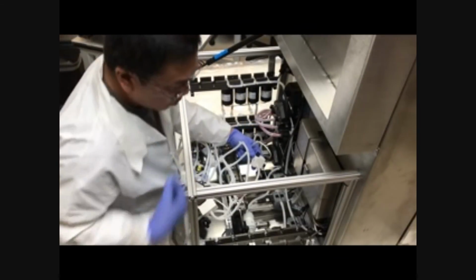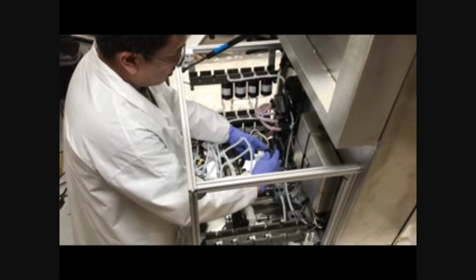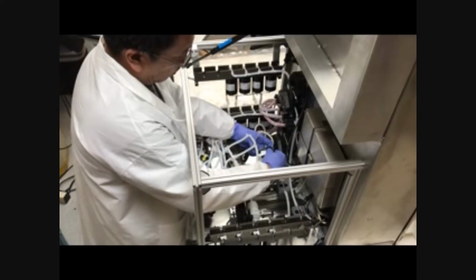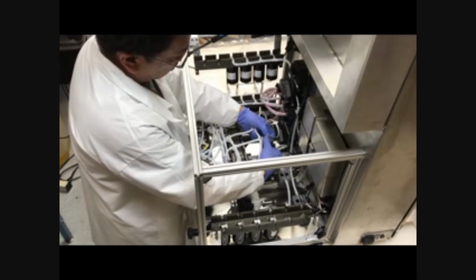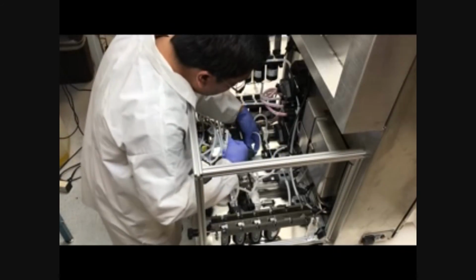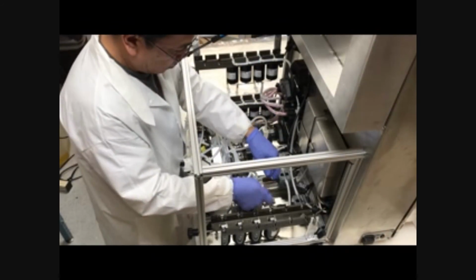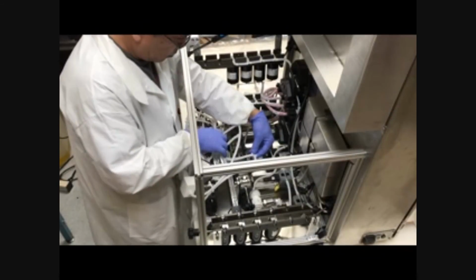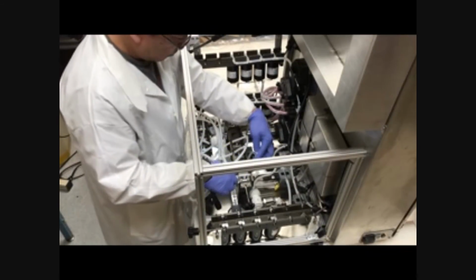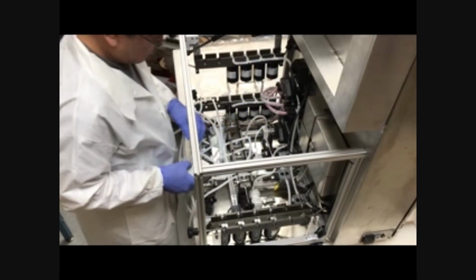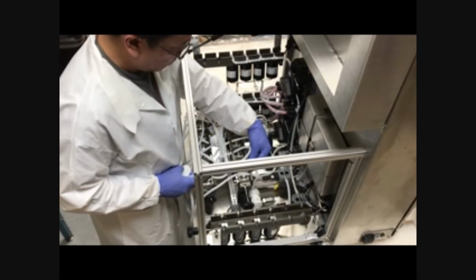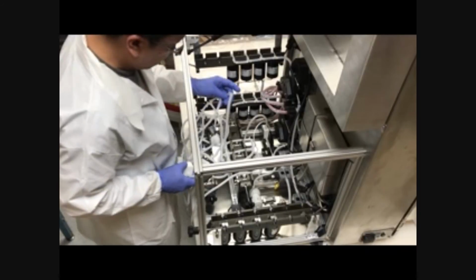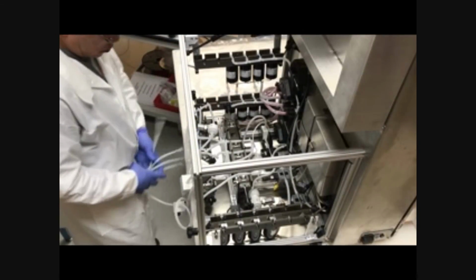Yeah, and the next one is the conductivity sensor that he attaches a bracket to. And then he's sliding it into its slot, which is pre-labeled. There. So the pre-column conductivity sensor is installed. So we now have the tubing being installed for that goes to the column, that goes to the air eject valve, and that goes for the pre-column device, which might be a filter or a bubble trap or anything like that.